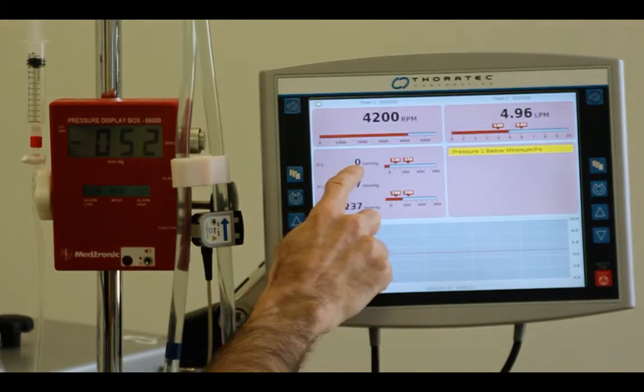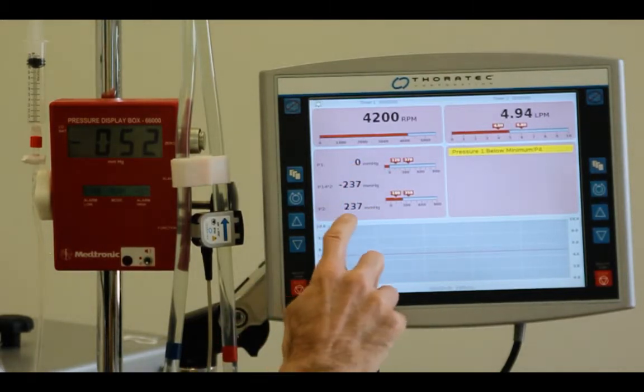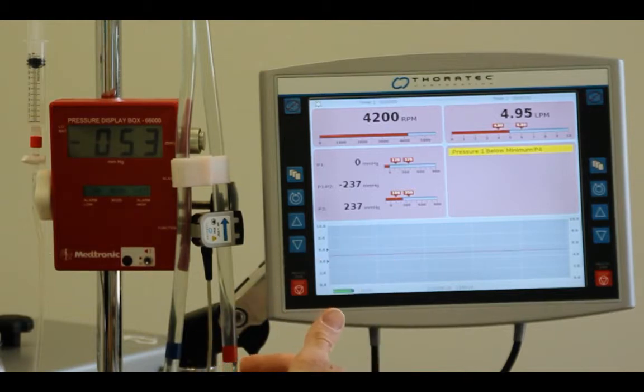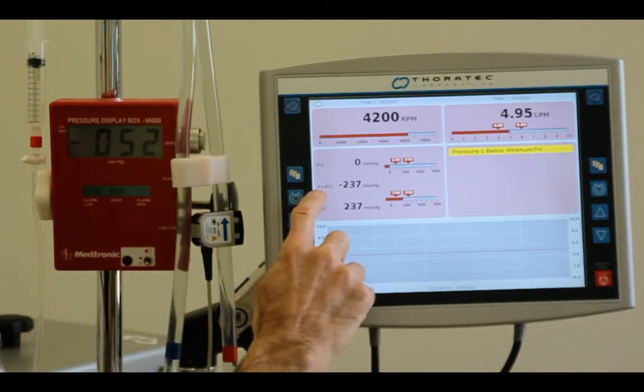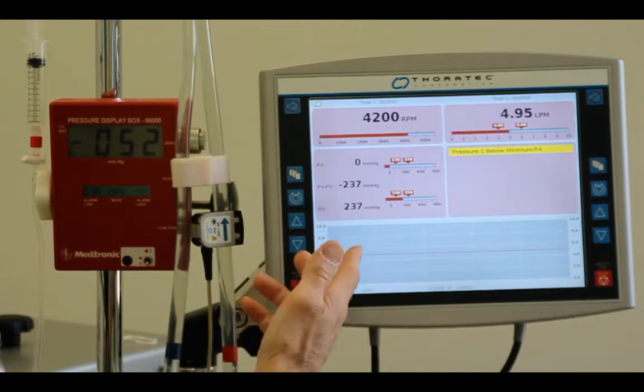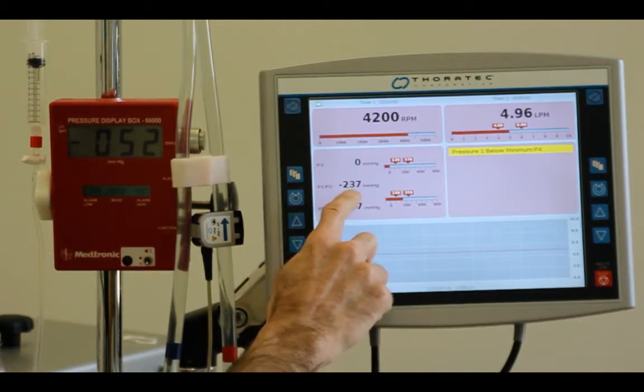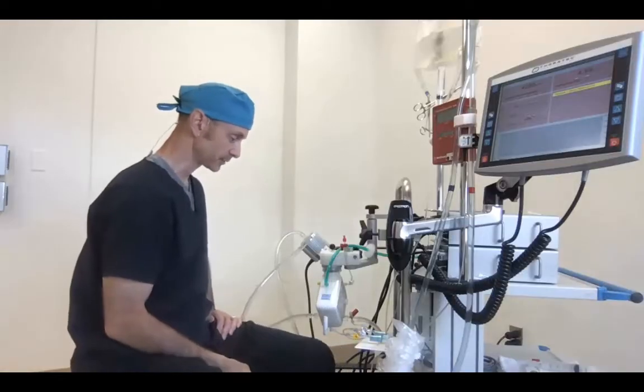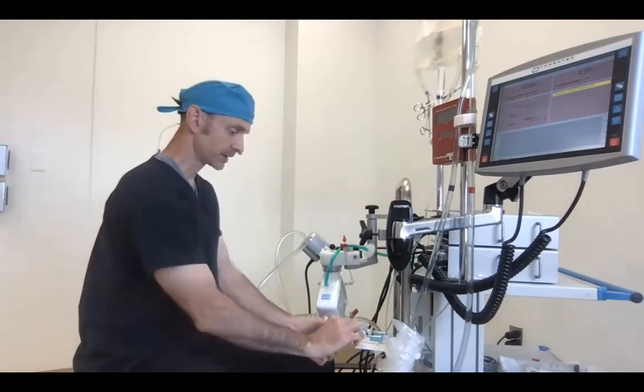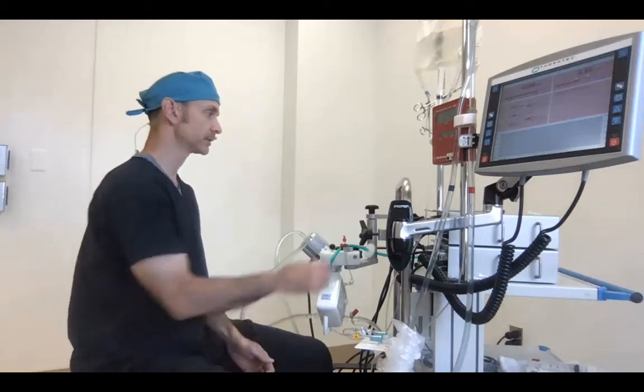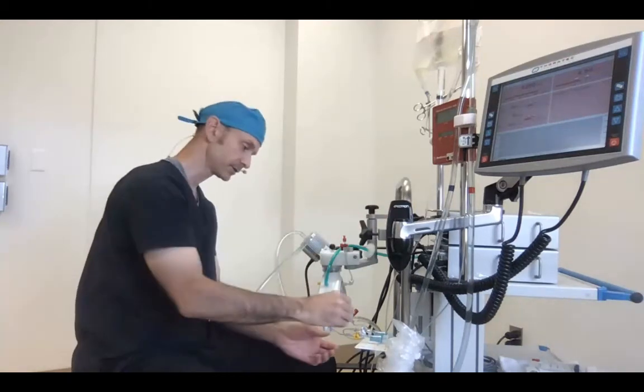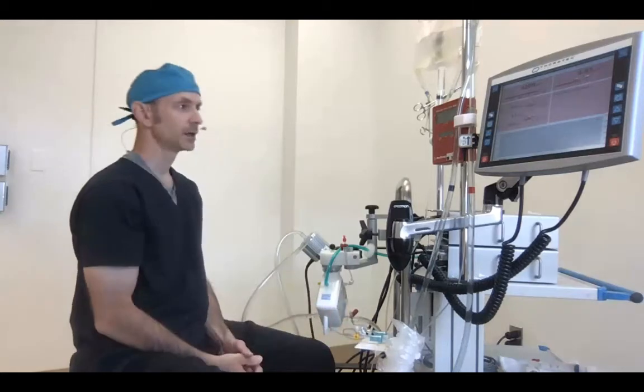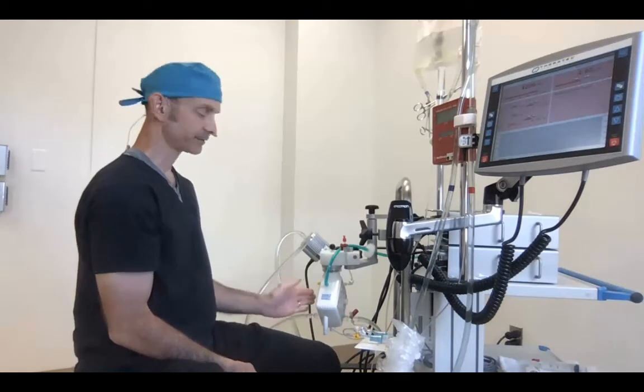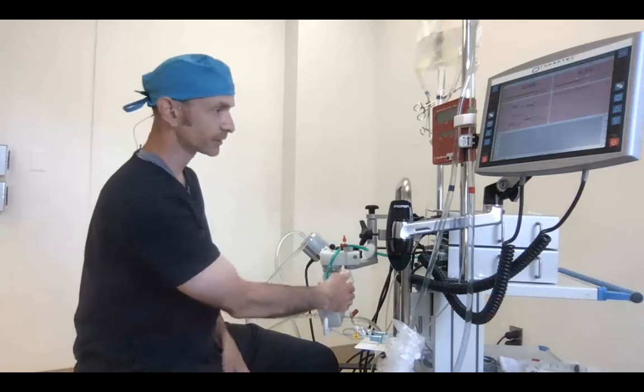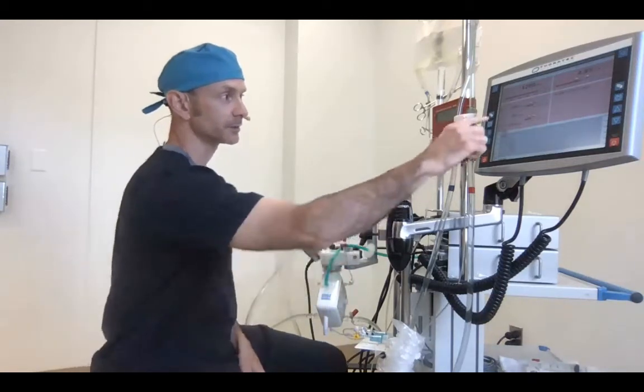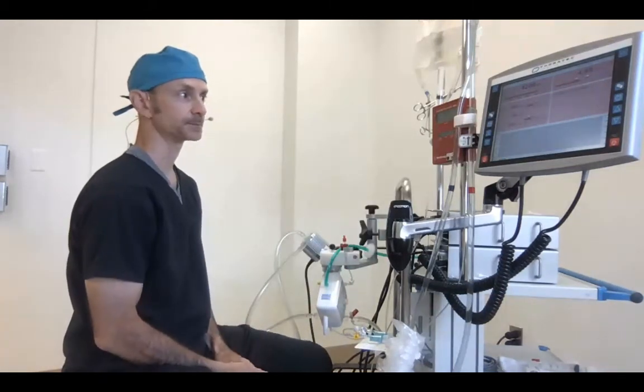Now we're reading 0 on P1 because we're still open to air, and we're reading 237 on P2. That's what it was reading previously. And we're getting a calculated number of P1 minus P2, otherwise known as the delta P. That delta P is minus 237. This is a subtraction of the two. So let's turn the stopcock here. We'll open up P1 and put our sterile cap back on to keep it clean. And we're reading 256 on the pre-membrane side and 237 on the post-membrane side, with a delta P of 19.